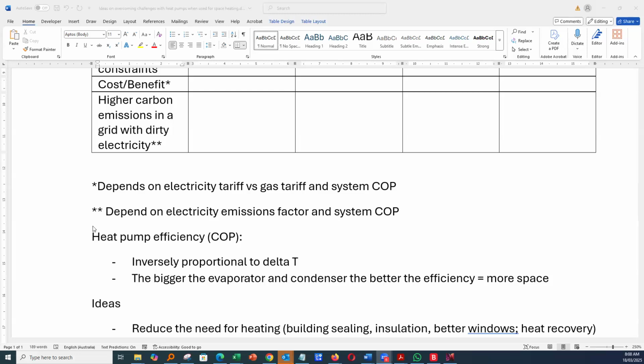So here are some ideas. Firstly, reduce the need for heating, because this upgrade could be challenged. This involves building sealing, insulation, better windows, and heat recovery. I just want to touch on the one with better windows. In many climates in winter, windows are useful if they're facing the direction the sun is at. That's either north in the southern hemisphere, or south in the northern hemisphere. You can get quite good radiant heat gain through those windows, but you want to be keeping that heat in. So there are some surface treatments on the windows, like a low emissivity coating, to keep the heat in.